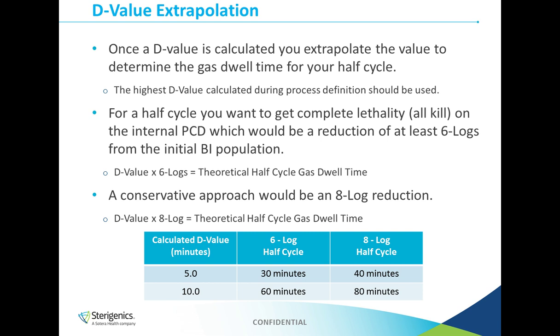Now for that half cycle, you're going to want to get complete lethality or all kill on the internal PCD. And traditionally, a BI with 10 to the 6 population is used. So in order to get all kill on that BI, you need to reduce that BI population down to 0, or in other words, you need to reduce that by 6 logs. So you take that D value that you calculated, you multiply it by 6, and you get that theoretical half cycle gas dwell time. And that's the time that you should get all kill on your internal PCD.